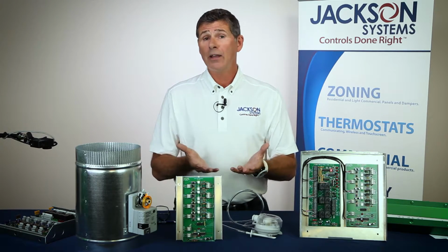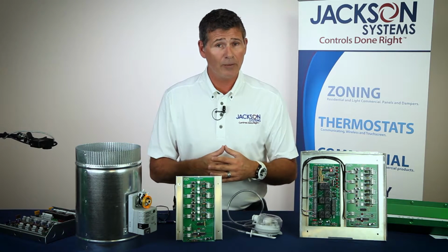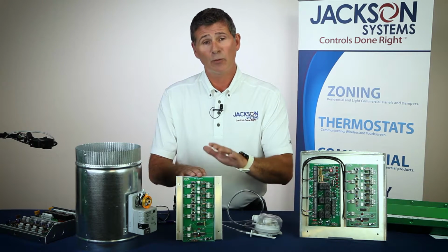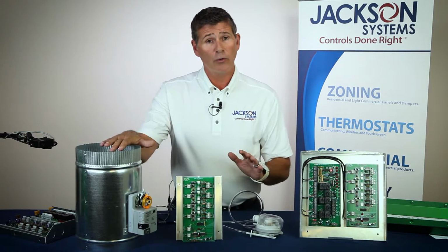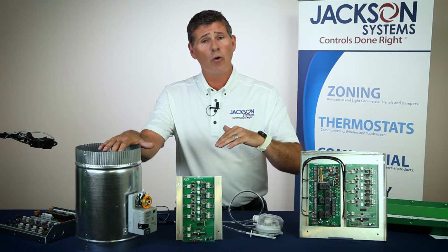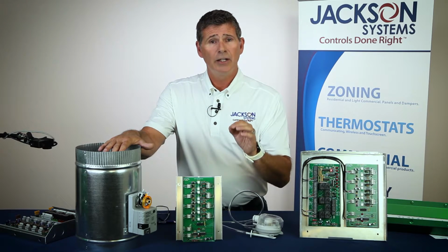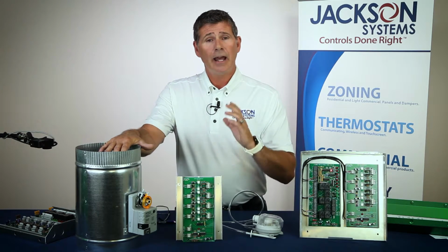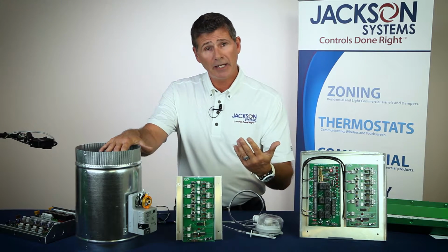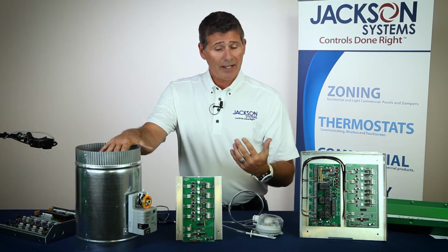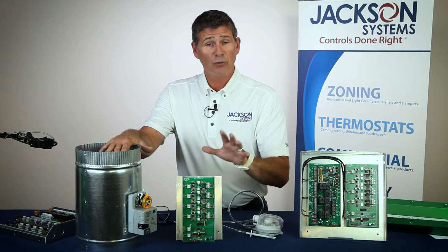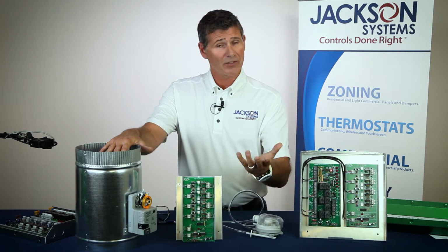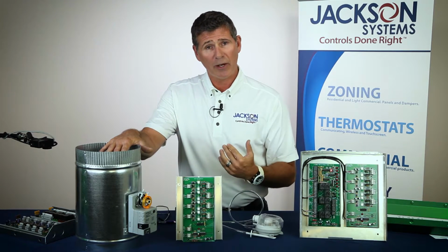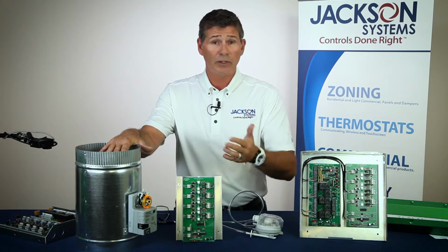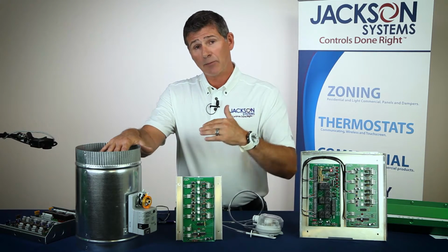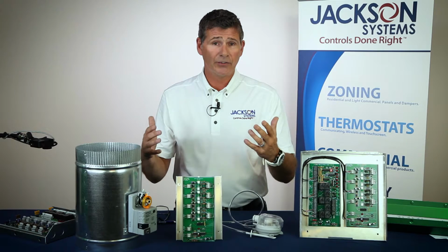Now if the static pressure rises to above 0.35 inches of water column, this panel is going to relay a message to the 2 zones that are closed and tell them to begin to bring those dampers open ever so slightly, just enough to relieve the static pressure in the system. Now, once those dampers are open and that static pressure is beginning to be released, every 60 seconds, this system is going to take a look at the static pressure within the system itself and make adjustments. If the static pressure is no longer there, the dampers are going to close. If the static pressure has, for whatever reason, risen over the last 60 seconds, the dampers are going to open just a little bit more to relieve that excess static pressure.